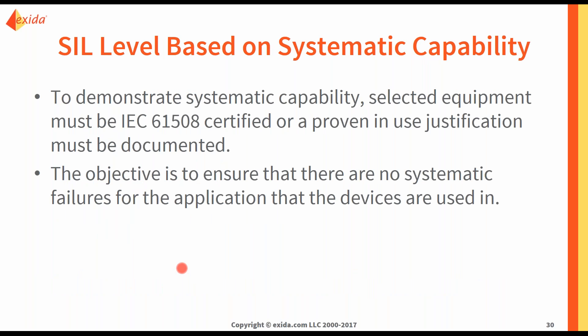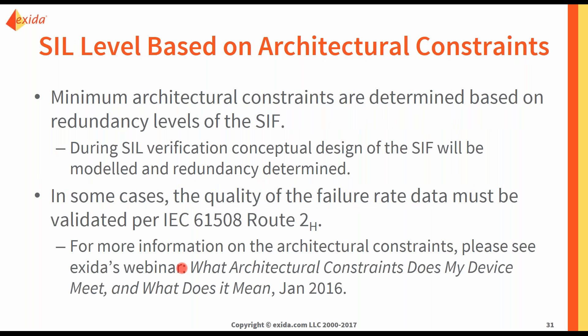To analyze SIL level based on systematic capability, equipment selected must be IEC 61508 certified, or a proven-in-use justification must be documented. The objective is to ensure no systematic failures for the application. For architectural constraints, minimum levels are determined based on redundancy in the SIF. During SIL verification, conceptual design is modeled and redundancy is determined. In some cases, the quality of failure rate data must be validated per IEC 61508 Route 2H.